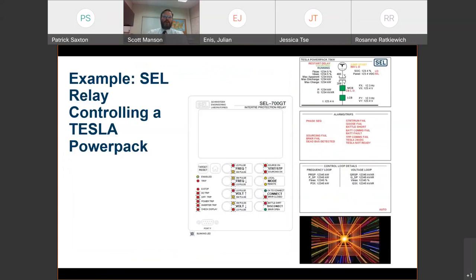Here's an example, right off the bat, of what you do with a modern multifunction device. This is the most common electronic device in the distribution and transmission system, an SEL relay. It's got the intelligence, in this case, to control a Tesla Powerpack. There on the right are the four screens that appear on the display of the relay, depending on the mode you're in. And the screen itself is augmented by the buttons below it. Those buttons are programmable, and the LEDs, we call them target LEDs, are programmable. They're programmed as a universal interface, in this case, for inverters. So these relays control inverters.